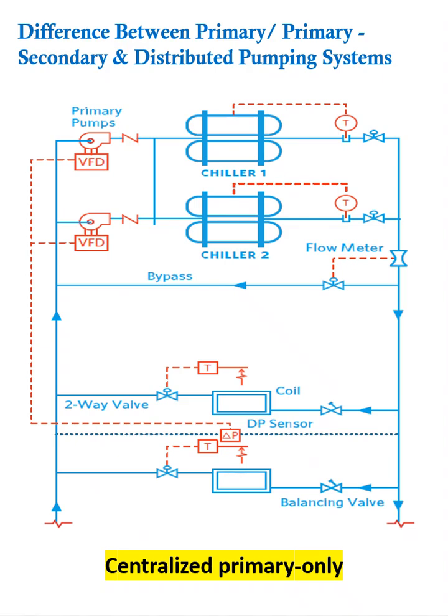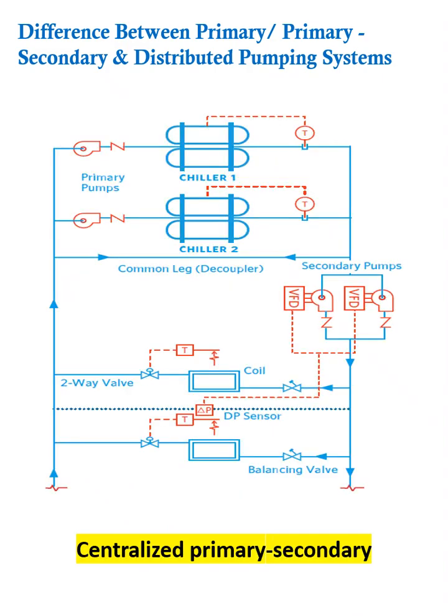Now, in the primary secondary variable system, you can see chillers are available, and the VFD is not connected to the pumps in the primary application. The VFD is connected to one more set of pumps called the secondary pump, and now the secondary pump becomes variable, pumping water to the load and the AHUs.